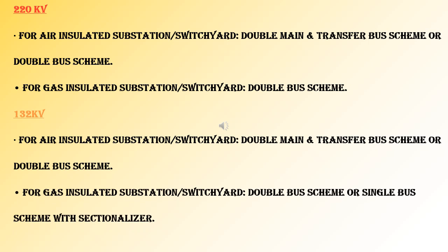In continuation of the summary of EHV substation switching schemes, the double main and transfer bus scheme or double bus scheme is used for an AIS substation. The double bus scheme is used for a GIS substation. For a 132 kV substation, the double main and transfer bus scheme or double bus scheme is used for an AIS substation. The double bus scheme or single bus scheme with sectionalizer is used for a GIS substation.